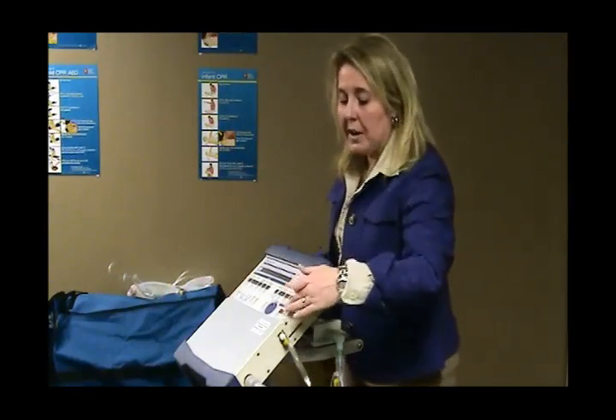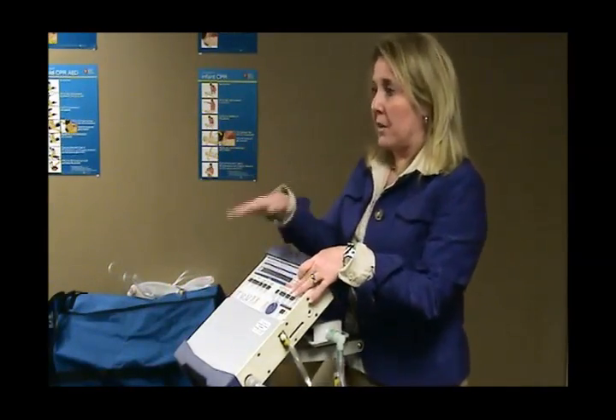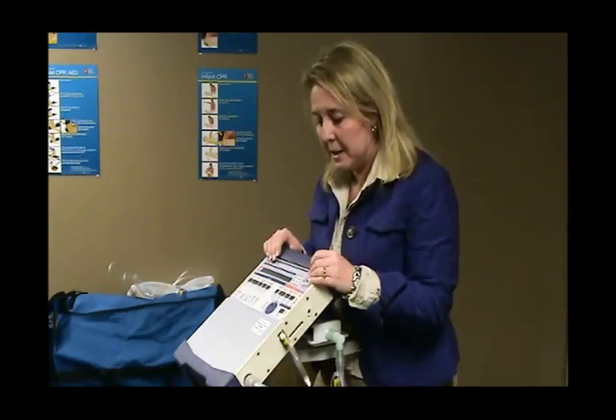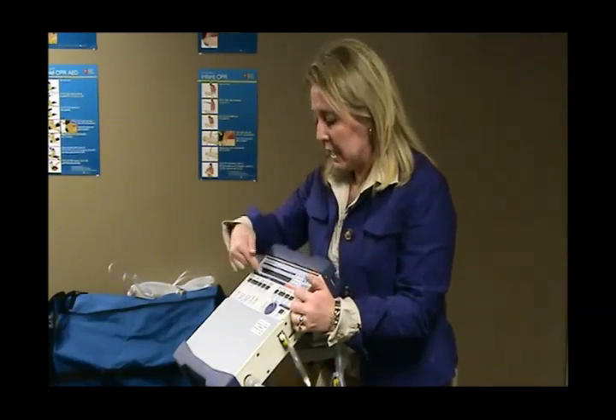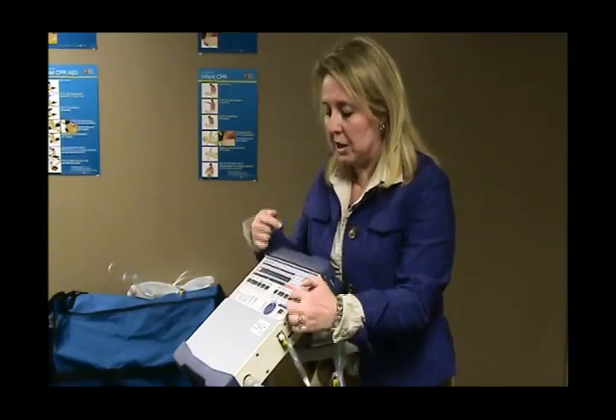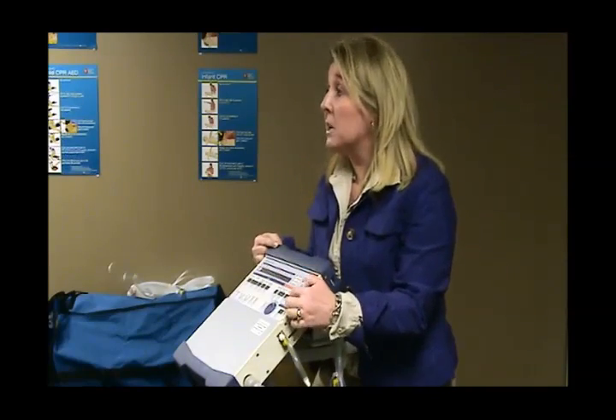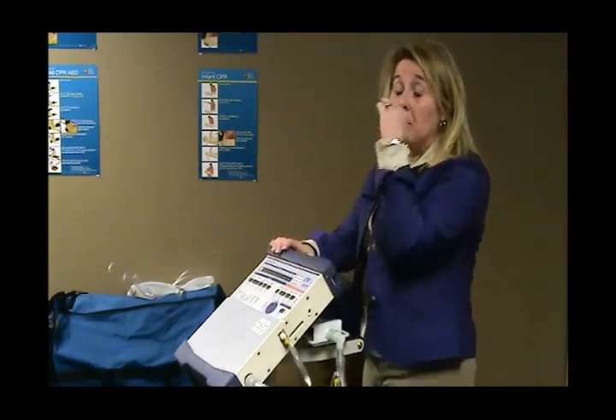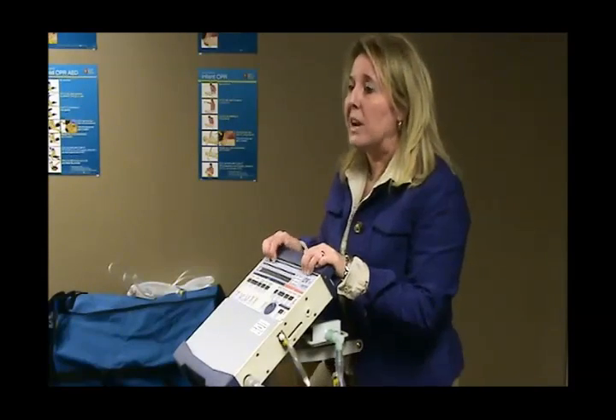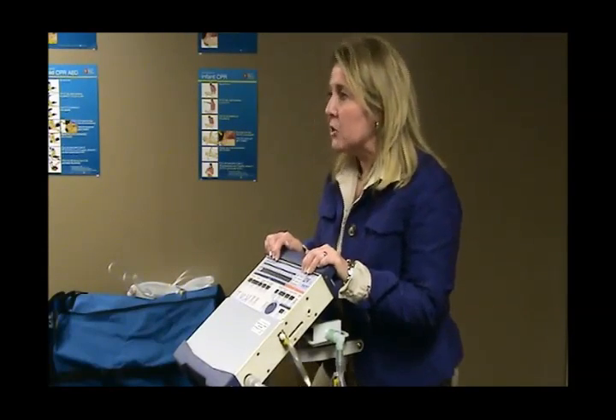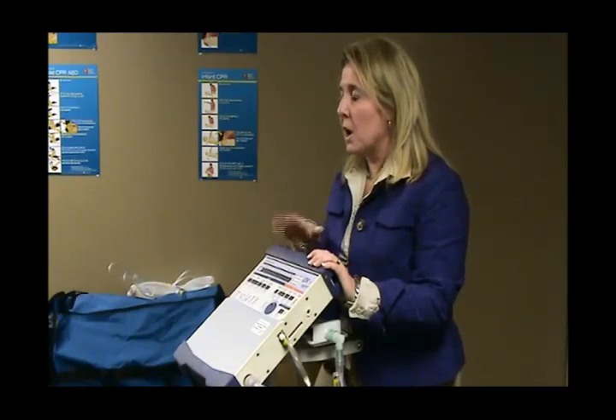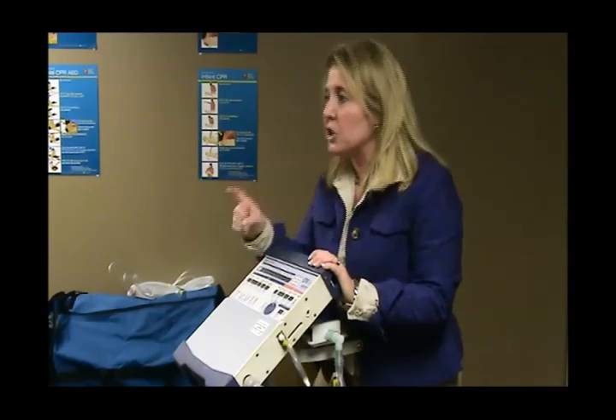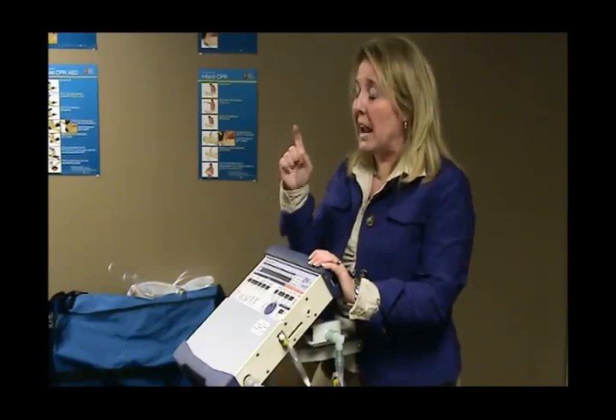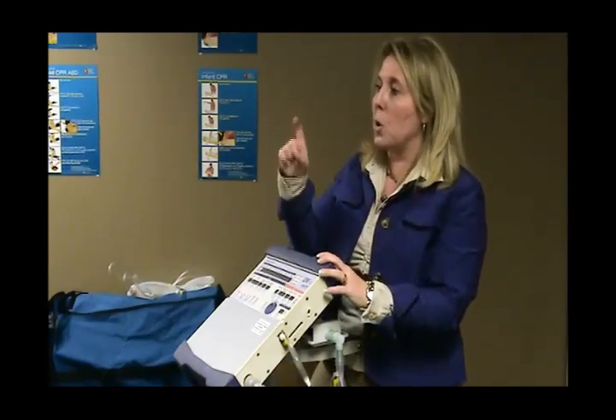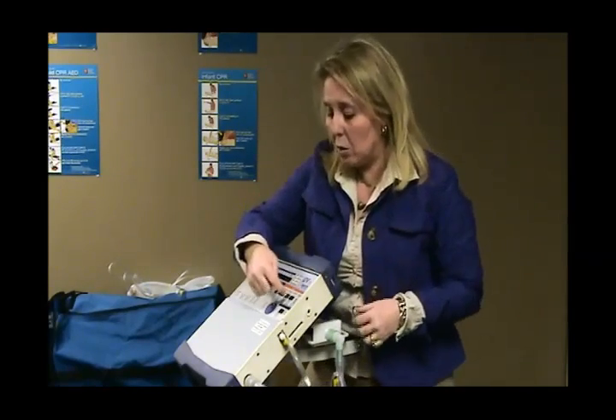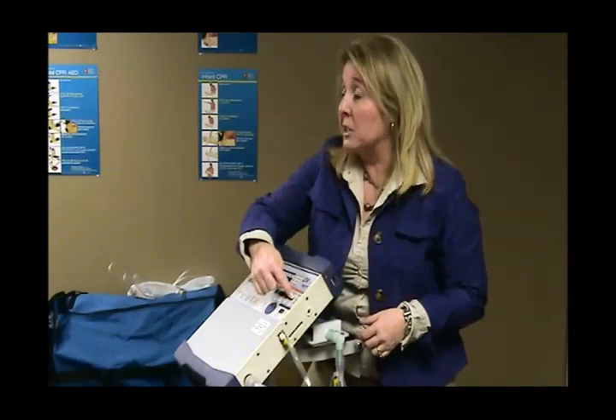Our ventilator measures, and all of our ventilators measure exhaled minute ventilation. There's a place for an alarm for it. It'll display what their exhaled minute ventilation is here. There's a low minute volume alarm that we set on here. That low minute volume alarm is very important if we are pressure only ventilating. So if we're not volume ventilating at all, volume plus pressure support, but we're pressure ventilating, either pressure control, AC, assist control, or pressure control with pressure support, that minute ventilation alarm is really important.